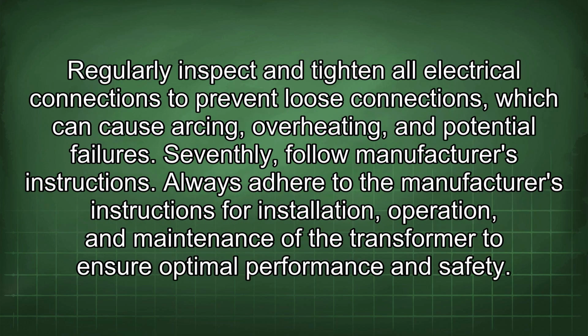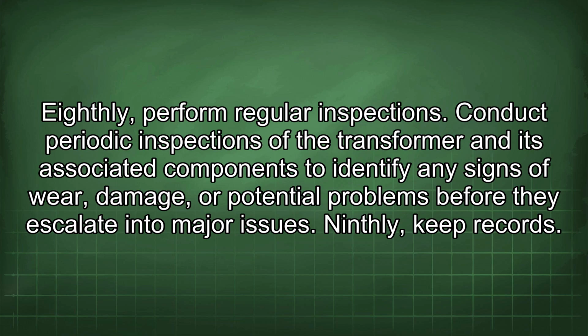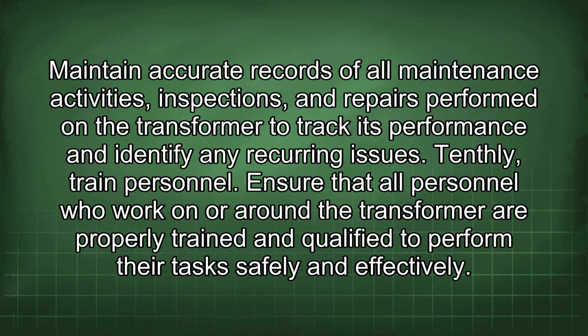Regularly inspect and tighten all electrical connections to prevent loose connections, which can cause arcing, overheating, and potential failures. Seventhly, follow manufacturer's instructions. Always adhere to the manufacturer's instructions for installation, operation, and maintenance of the transformer to ensure optimal performance and safety. Eighthly, perform regular inspections. Conduct periodic inspections of the transformer and its associated components to identify any signs of wear, damage, or potential problems before they escalate into major issues. Ninthly, keep records. Maintain accurate records of all maintenance activities, inspections, and repairs performed on the transformer to track its performance and identify any recurring issues.